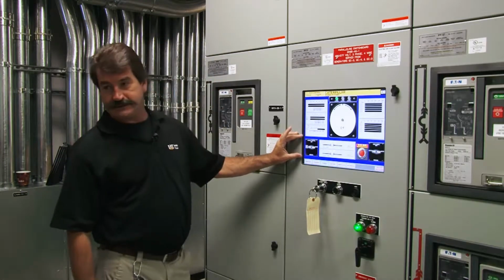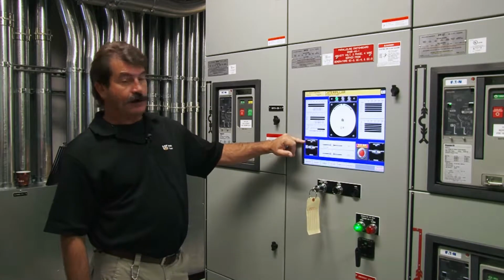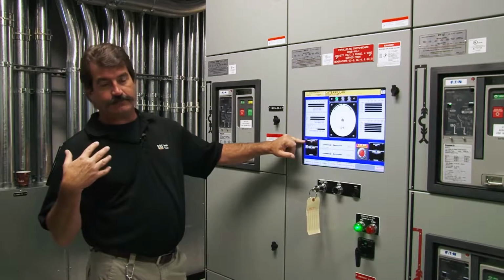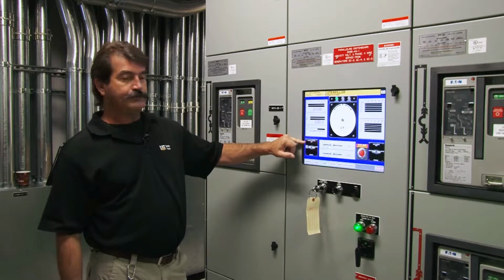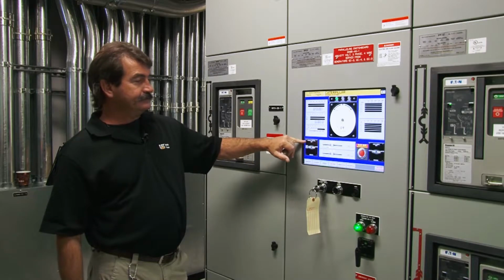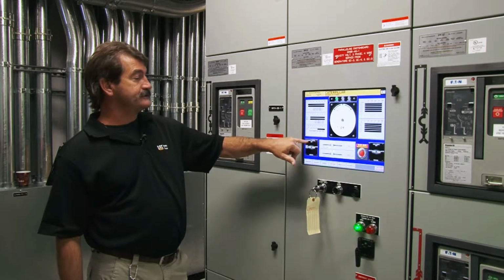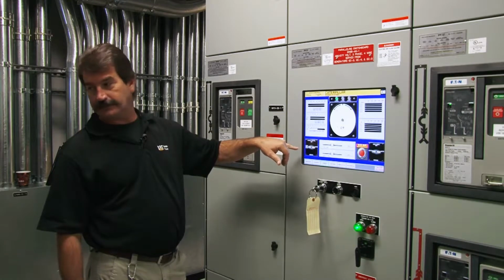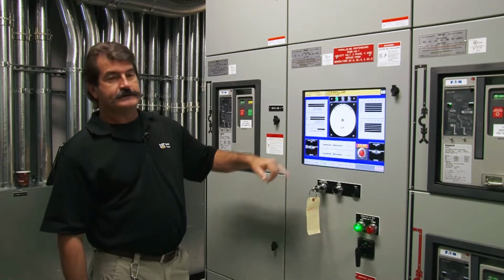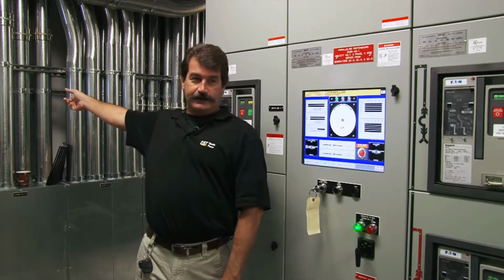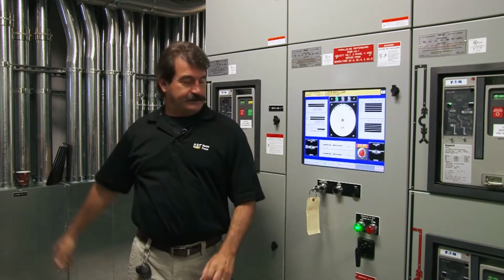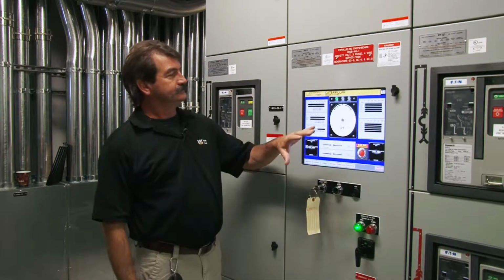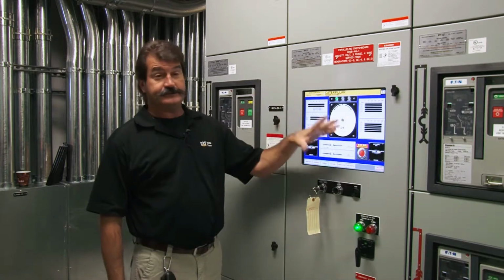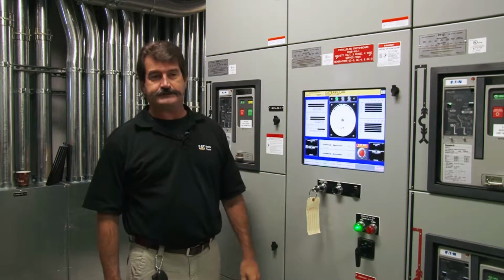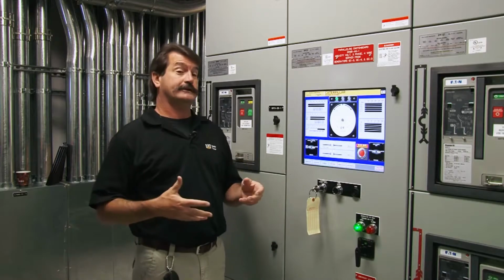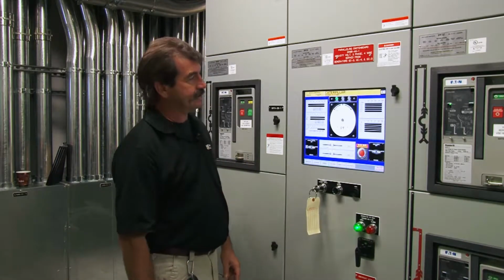As far as if you do have a shutdown, for the engine to reset the shutdown, you want to take it to off. Okay, once you take care of whatever shut that gen down, take it to off, then take it back to auto. Normally it says off/reset, and I don't know why they stopped doing that, and that's what it does. So even if it shuts down out there, you've got to go off reset out there, and then you've got to come in here and go off reset. Pretty much anytime the gen shuts down, you just count on doing off reset at our place. Whether they shut it down, we shut it down, whatever, off reset. That'll take care of it.